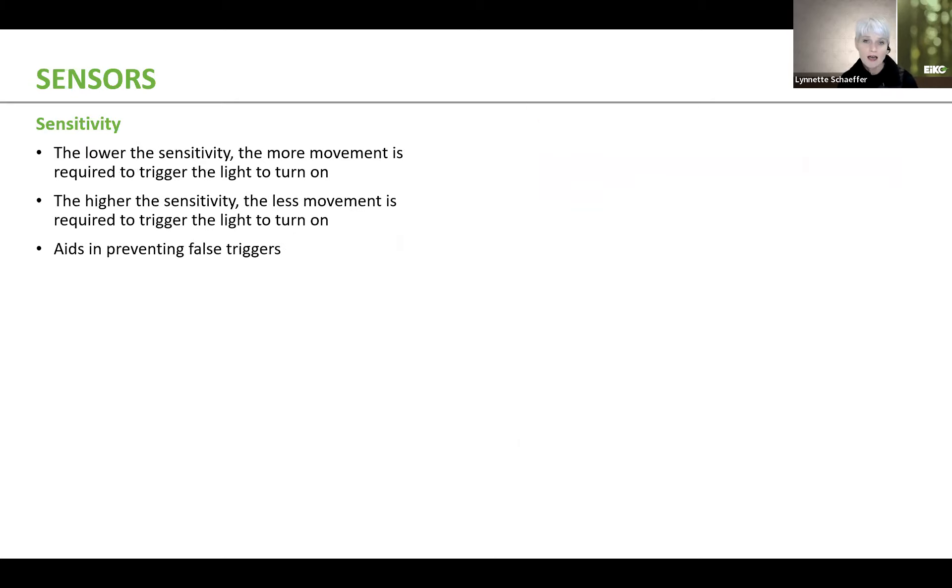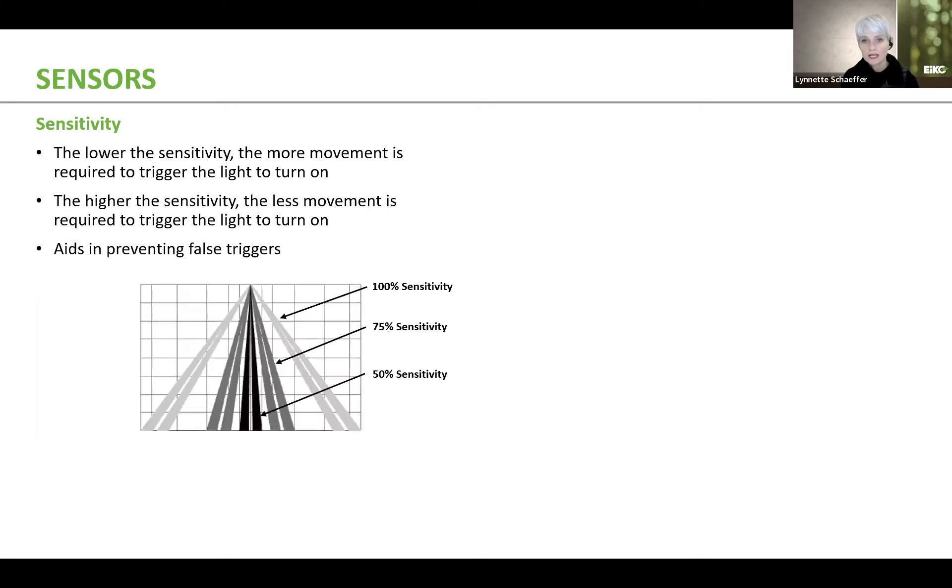Also, as I mentioned, some sensors have the ability to set sensitivity. And this is important because it aids in preventing false triggers. Now, as you watch this animation, you will see that the light fixture will turn on depending upon the sensitivity, how the sensitivity is set for the sensor. So at 100%, the fixture will turn on fairly quickly. At 75% sensitivity, it takes a little bit longer, you got to get a little closer to the fixture. And at 50%, it takes even longer for the fixtures to turn on. You almost nearly need to be underneath the fixture for it to turn on. The reason that people like to be able to set the sensitivity is because it aids in preventing false triggers.